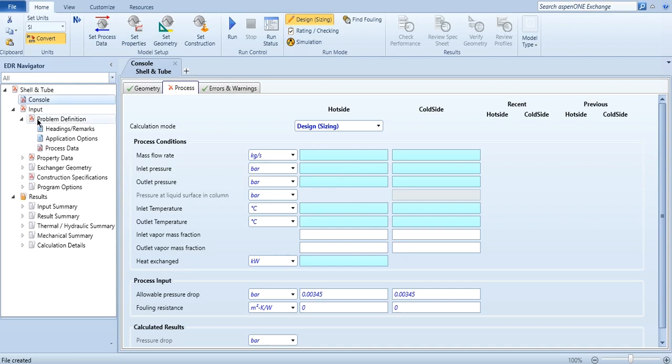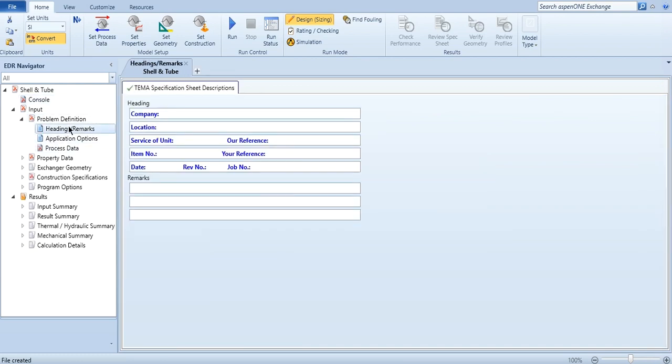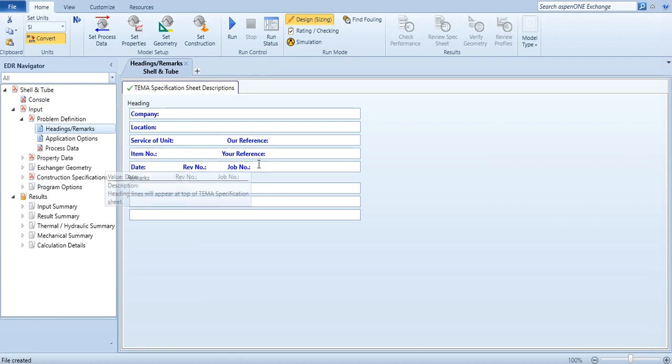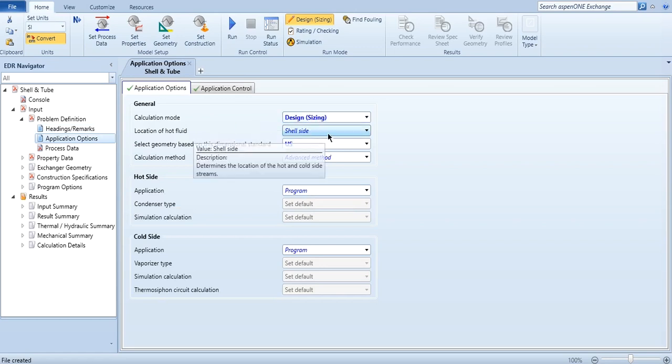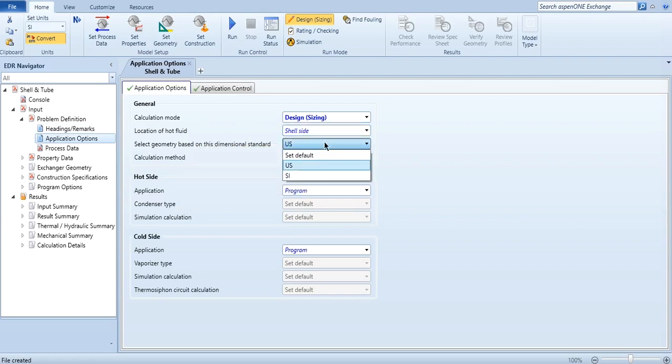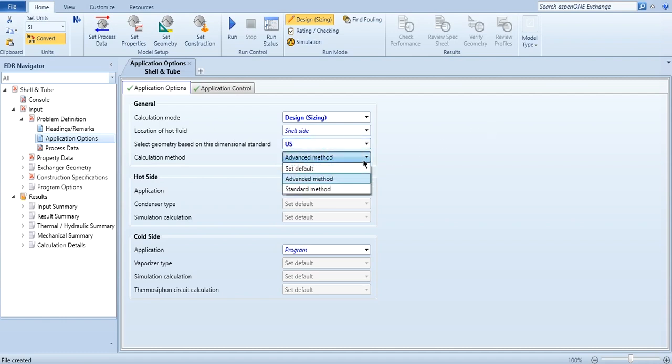This is one way of doing it. Another way of doing it is to click on problem definition. And in headings remarks you can click which is the company location, service of units, and so on. This information you can fill over here. Then the application options, that the calculation mode is design. The location of hot fluid, by default again it is shell side. Select geometry based on this dimension. If you want to select SI, you can select here. If you want to pick US, it is updated as well. And then the calculation method is advanced or standard. Obviously, we want always advanced method.